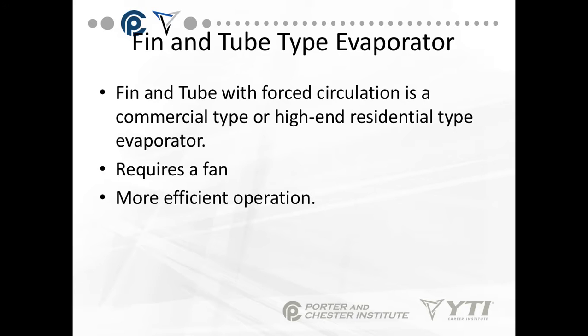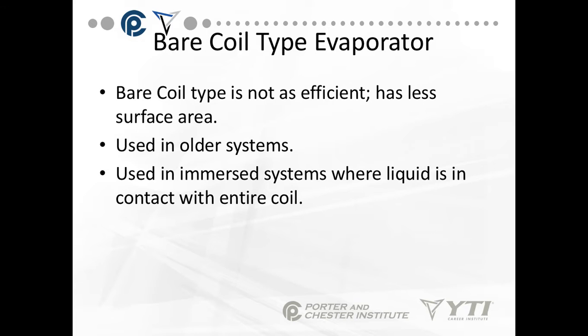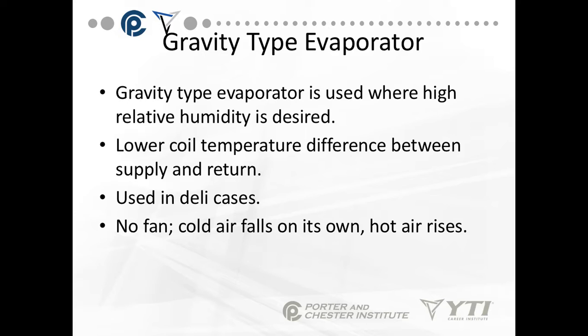The fin and tube type evaporator is the most frequent one you'll see, used with forced circulation in commercial or high-end residential systems. It requires a fan and has more efficient operation because I don't need as large a surface area since I'm moving a lot of air across the coil. The bare coil type has no fins, so it's less efficient with less surface area, and is used in immersed systems where liquid contacts the entire coil. The gravity type is used where high relative humidity is desired, has a lower coil temperature differential, and is used in deli cases — cold air falls and hot air rises, creating its own air circulation pattern without a fan.